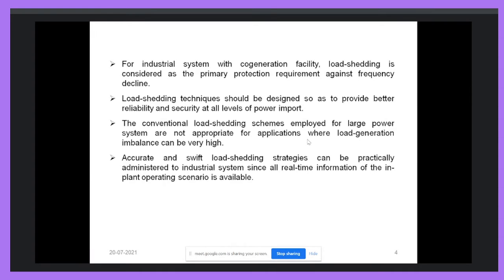Under frequency relay based load shedding is not accurate, because this technique is designed on the basis of the worst operating scenario. For the maximum mismatch, we design the frequency based load shedding technique. If there is a smaller mismatch, the relay will still disconnect the preset load from the system. So these relay based load shedding techniques are not accurate and not reliable. For that, artificial intelligence based techniques are more reliable and more accurate. We will see in further slides how these intelligent techniques are more accurate compared to relay based techniques.